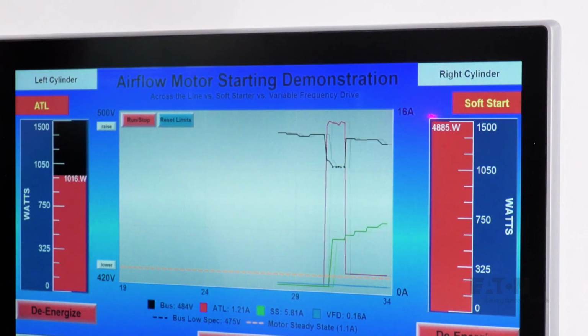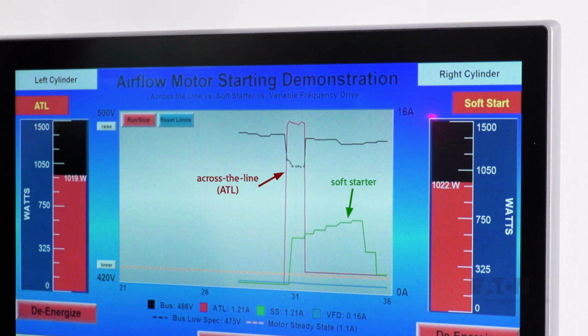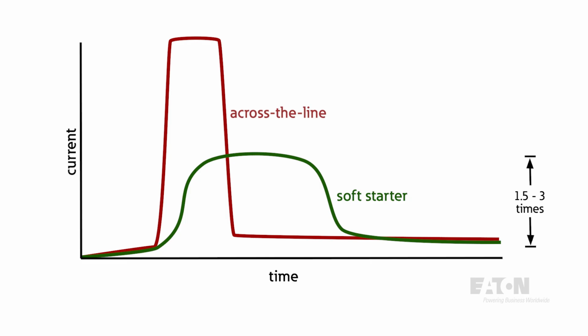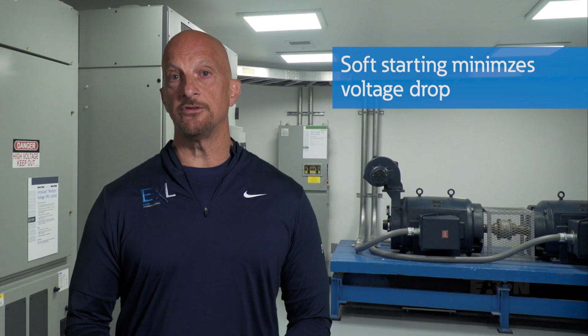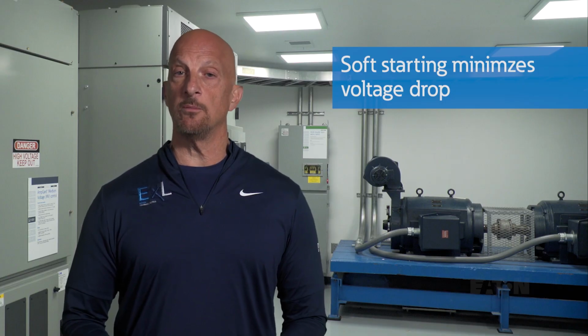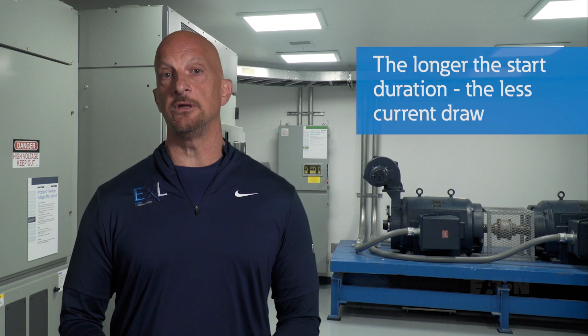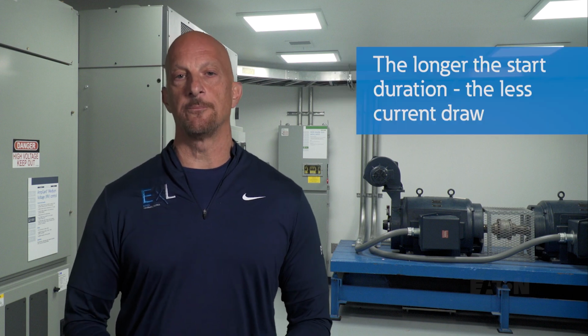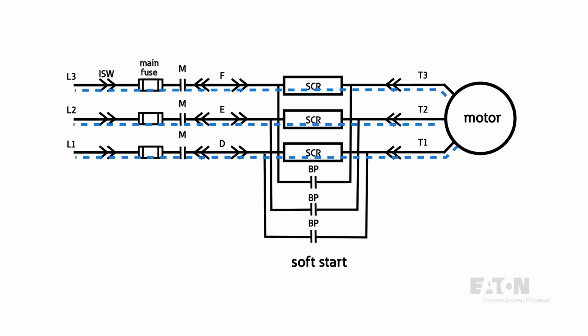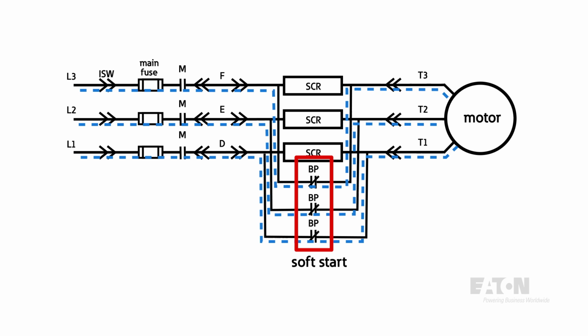With a soft starter, the motor draws significantly less current during starting, on the order of 1.5 to 3 times nominal current instead of 6 to 8 times. This minimizes the voltage drop issues and is programmable across the range of starting times. Usually, the longer it takes, the less current you'll draw. Once the motor's overcome inrush and it's operating at full speed, the soft starter will automatically transfer across the line with the bypass contactor. This allows the motor to operate at nominal 60 Hz speed after it's up and running. To turn off the motor, you simply trip the bypass contactor.